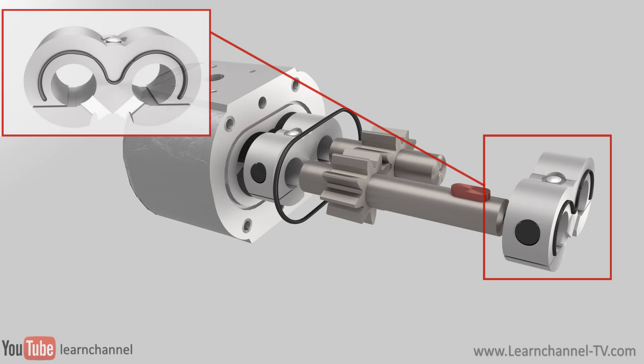When the pressure becomes too high, the oil comes up through the bearing clearance and goes through the notch back to the inlet. This way, the pump protects itself against being damaged, but the volumetric losses also increase with high pressure.